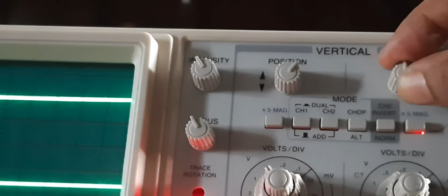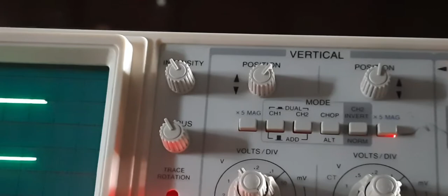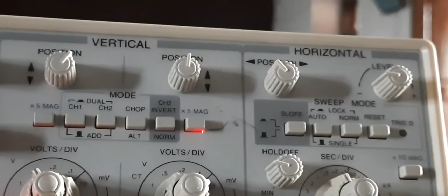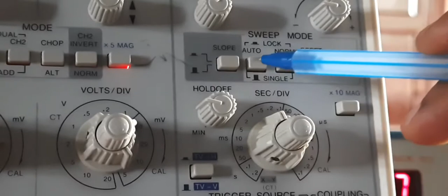Then this is a vertical position adjust. Vertical position adjust for the first channel, and this is a vertical position adjust for the second channel. This is a horizontal adjust for both the channels together. You can use the level adjust and the hold off for holding an AC signal in a constant mode. Then these I have left out. Thus you can put it in your auto mode. Then this is time per division. Here it is millisecond range, here it is second range, and here it is microsecond range. This is a reference knob. It should also be in the calibrated position. This into 10 magnification, don't use it unless it is necessary. Release position is fine so that there is no multiplication at present.